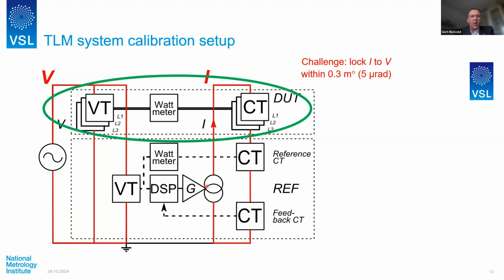One of the things that I learned from Eddie So, the late Eddie So from NRC Canada, is that this calibration is so important that, should you find that the system of the customer really has a large deviation, it is not an unlogical question that the customer says, well, what about your system? Are you sure that my system is deviating? Are you sure that not your system is deviating? So to that end, we add another verification measurement with a second current transformer and a reference wattmeter, so that we can compare the readout of our current generation and measurement system with, again, an additional wattmeter and CT. So we have two readings, and that is found extremely relevant in practice and also extremely useful.